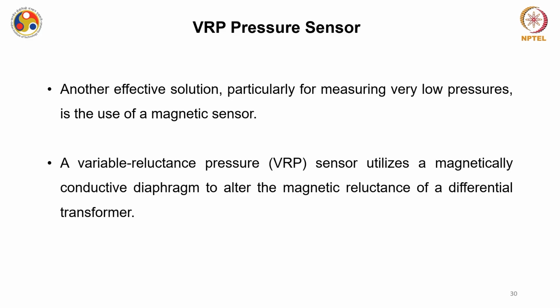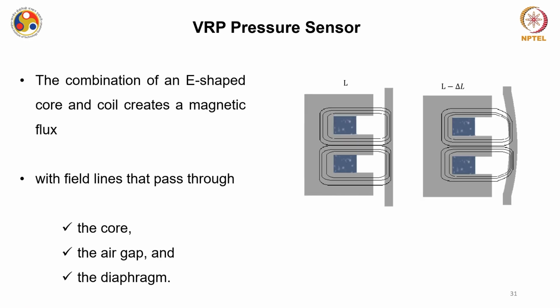One example of magnetic pressure sensors is the variable reluctance pressure sensor, which utilizes a magnetically conductive diaphragm to alter the magnetic reluctance of a differential transformer. The combination of an E-shaped core and coil creates a magnetic flux; this is one example of a VRP sensor. The combination of this E-shaped core and this coil is creating a flux here, with the field line passing through the core and also through the air gap, this is the air gap I am talking about, and this is the diaphragm.